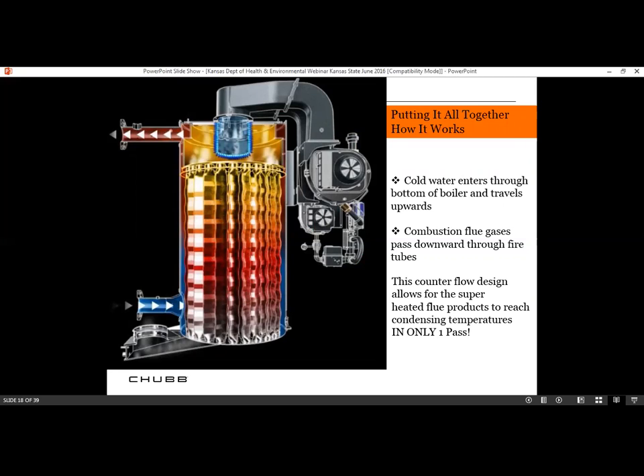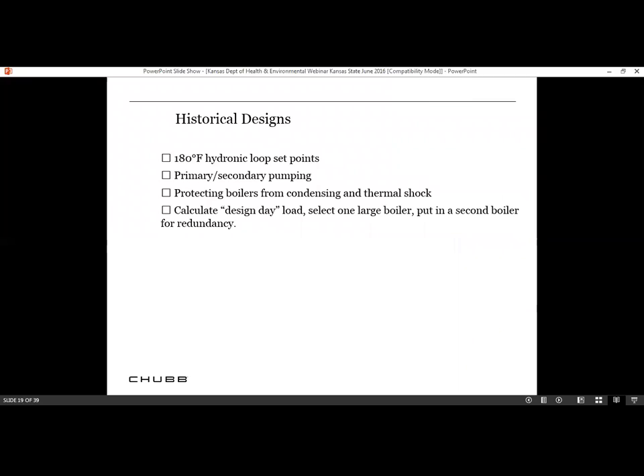If you look at the boiler that Keith had, naturally those are high pressure boilers, but those were 3-4 pass boilers. These are all one pass boilers, and makes it a little bit more efficient. Plus it's hot water. He had steam, high pressure steam. Historically, we've always designed boilers with 180-degree hydronic loop set points. We had primary and secondary pumping, protecting boilers from condensing and thermal shock. That was always our goal. We didn't want boilers to condense because it caused corrosion, and we didn't want to add water into the system, that cold water, because it caused thermal shock. And these new designs, those are not problems any longer.